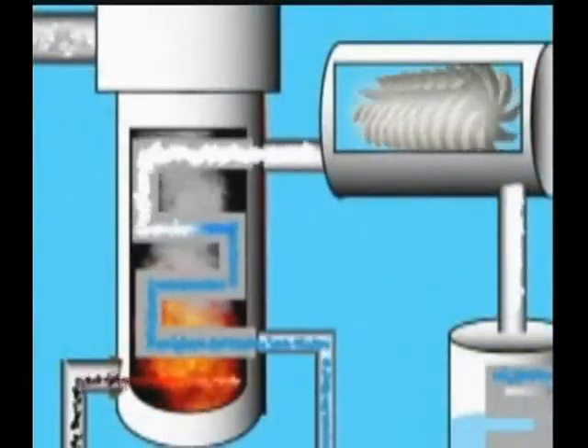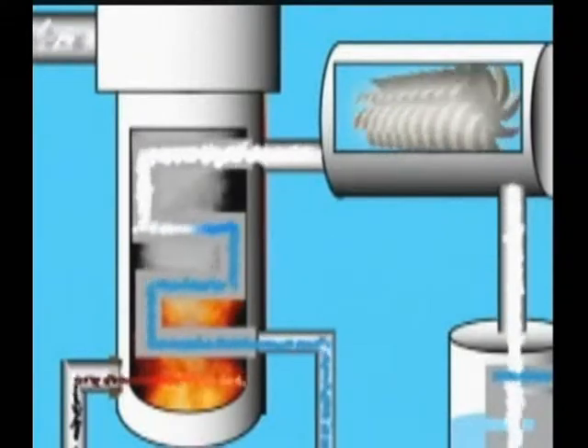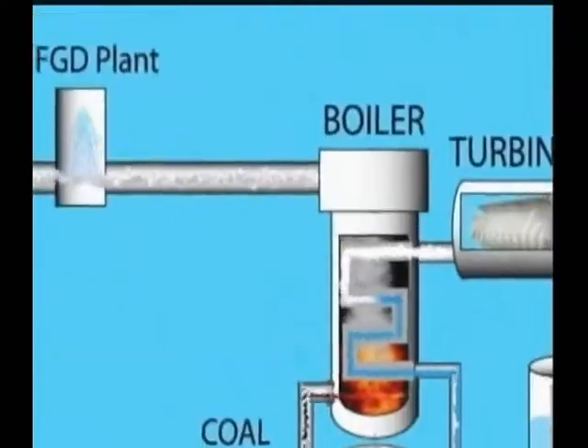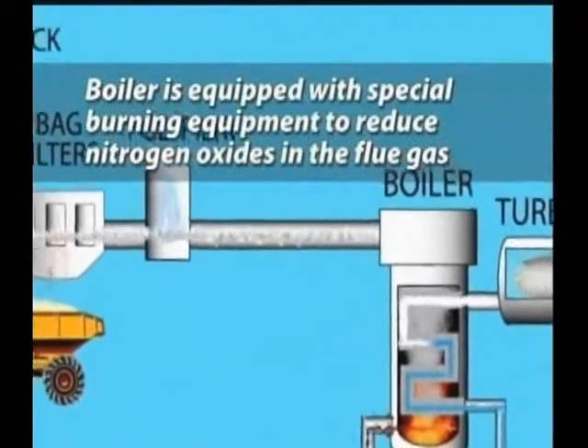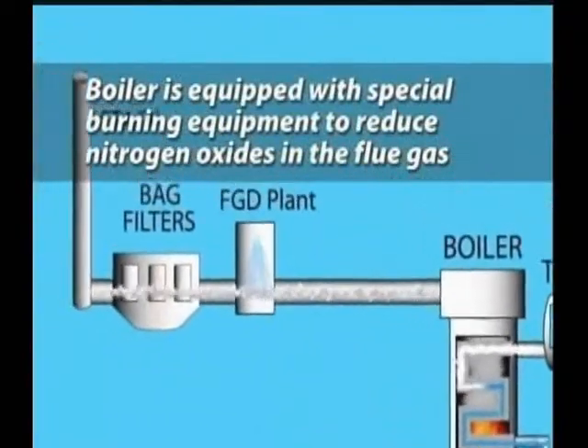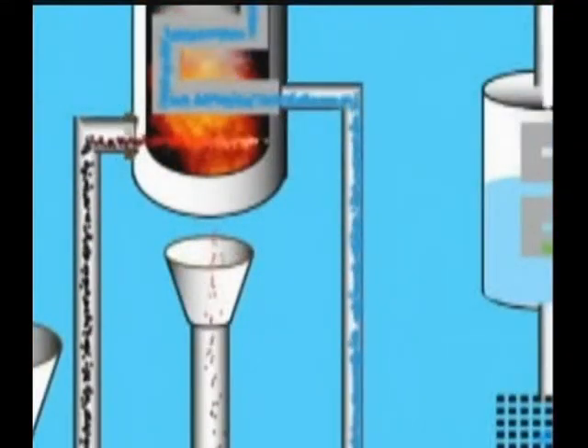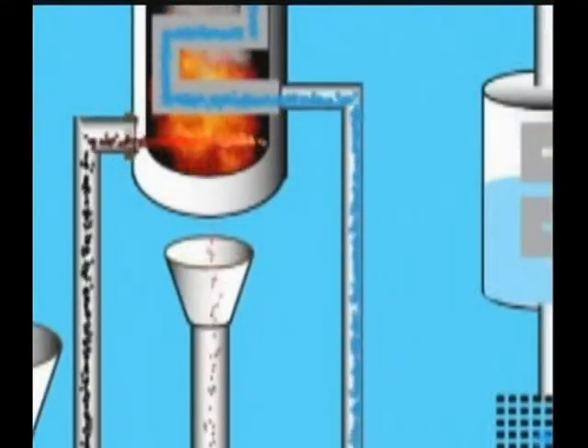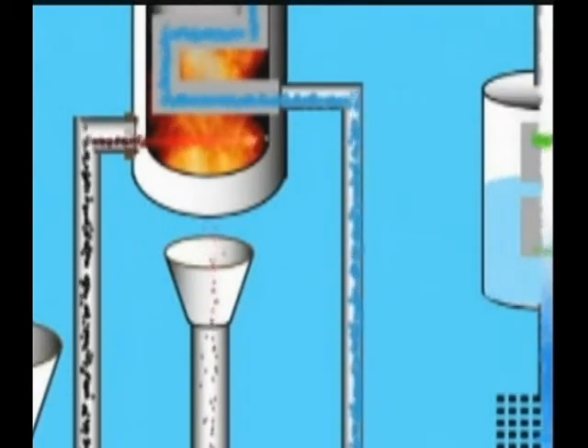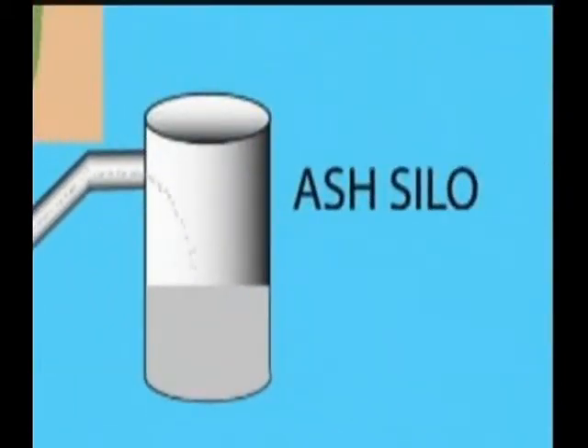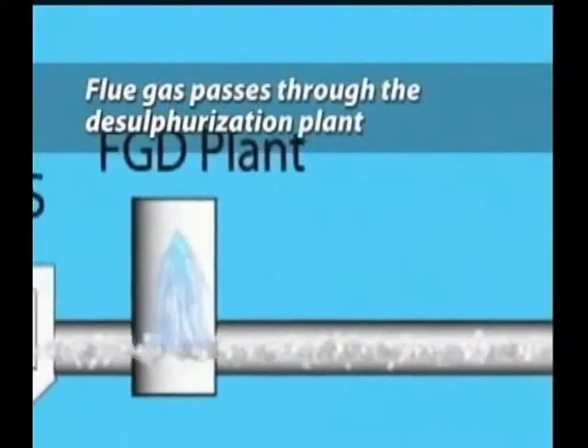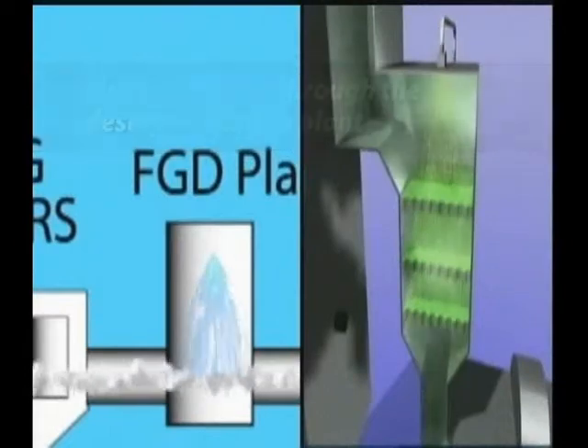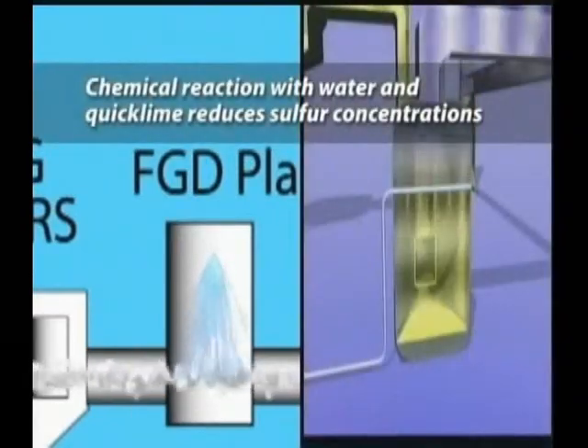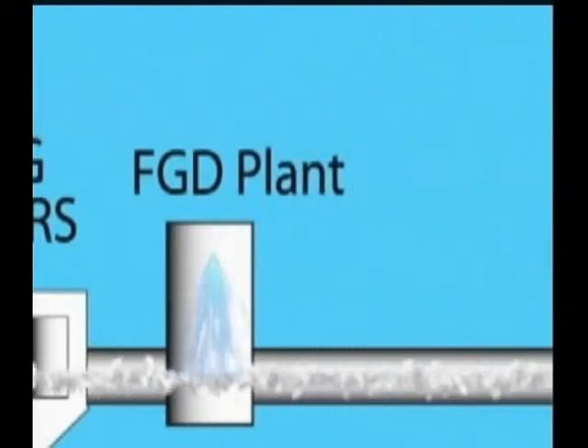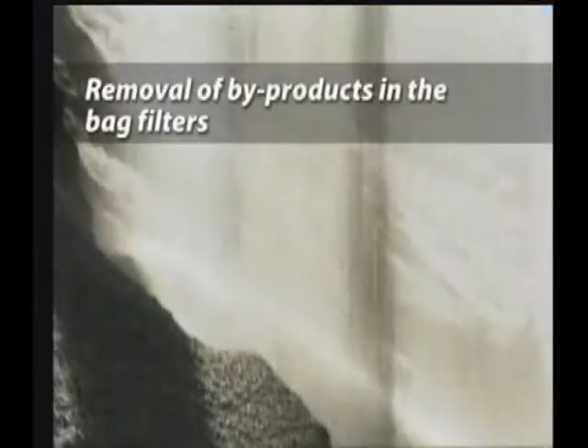Apart from flue gas, the burning of coal in the boiler furnace produces residues of fly ash and bottom ash. Also, the boiler is equipped with a special burning equipment designed to reduce nitrogen oxides in the flue gas. Bottom ash is removed from the furnace in a wet scraper. It will be deposited in a specially prepared disposal area. The flue gas with fly ash in suspension passes through the flue gas desulfurization plant, whereby a chemical reaction with water and quicklime causes sulfur concentrations to be reduced. The resulting byproduct of fly ash and gypsum from the reaction are removed in the bag filters.